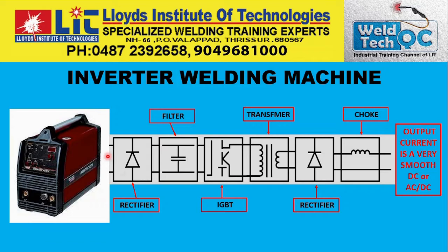So here, unlike the cases of the transformer or rectifier, the AC input current directly enters into a rectifier. The input AC current immediately passes through a rectifier which changes the AC to DC. This current at this stage is not smooth, but rippled and still high volts and low amps, and not suitable for welding. This needs to be filtered out here.